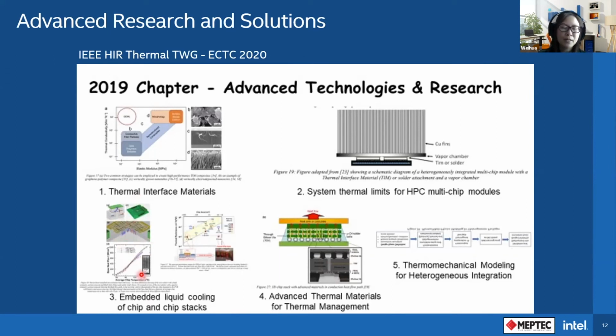There's a paper from Purdue looking at manifold microchannels - very small, narrow, high aspect ratio microchannels - reporting over 1,000 watts per centimeter square cooling capability. And a paper from Stanford looking at small scale two-phase on-chip cooling also achieved greater than 1,000 watts per centimeter square, demonstrated on a very small silicon area.